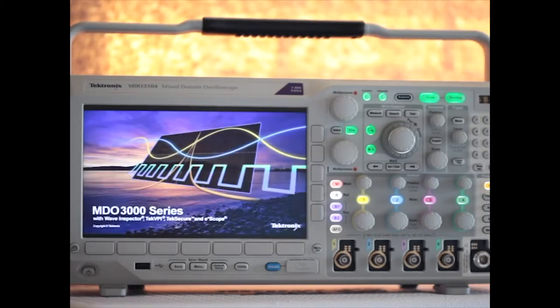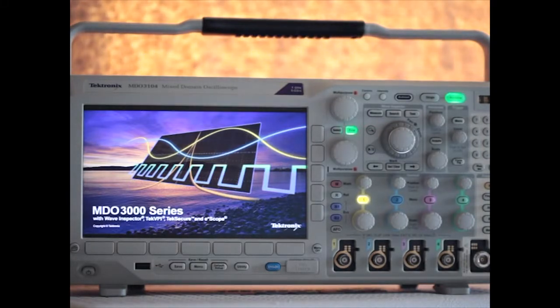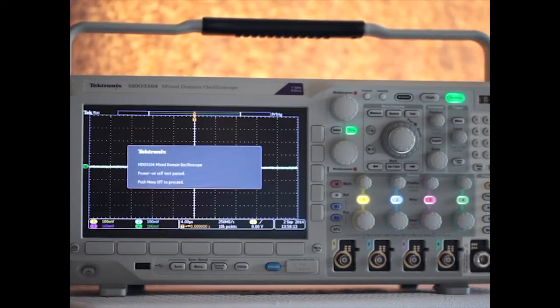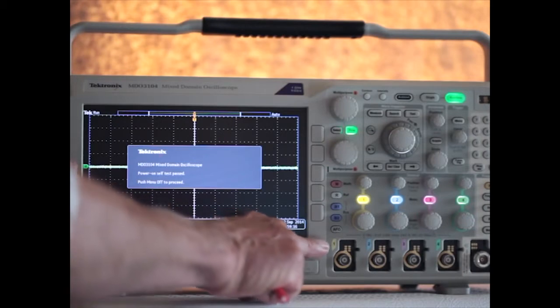Like lots of equipment in our cyber world, the MDO 3104 takes a little while to boot up. Incidentally, prior to performing a really critical or sensitive operation, it is a good move to warm up the instrument, including probe, for 20 minutes, more or less, depending on the ambient temperature. When the MDO 3104 is finished booting up, a box announcing that fact appears on the screen. The box will disappear after a few minutes, but if you want to hurry right along, push menu off.